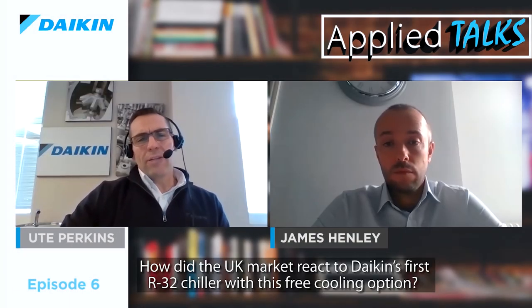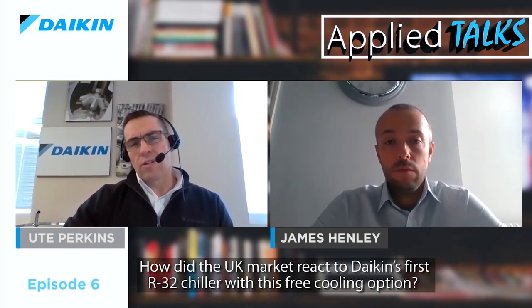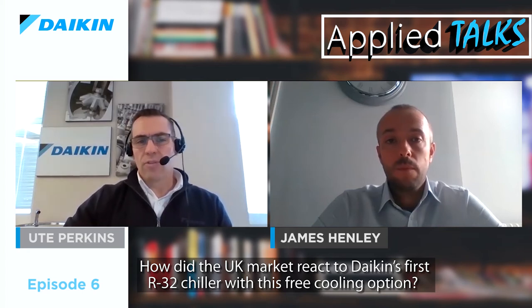Well, how did the UK market react to Daikin's first R32 chiller with this free cooling option? The UK market is really excited about the technology. Firstly, by the replacement of 410A refrigerant with the lower GWP R32, but also due to the free cooling technology.